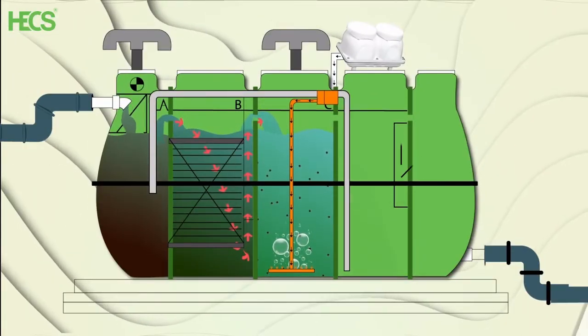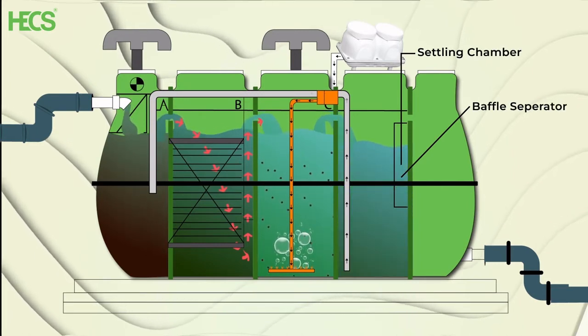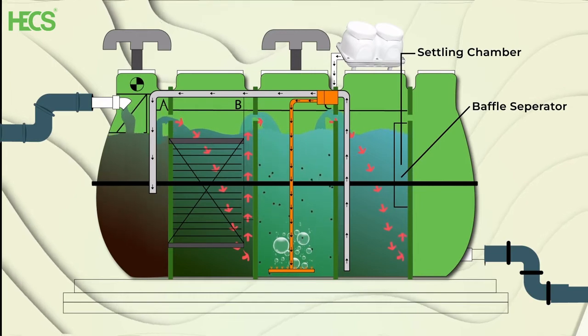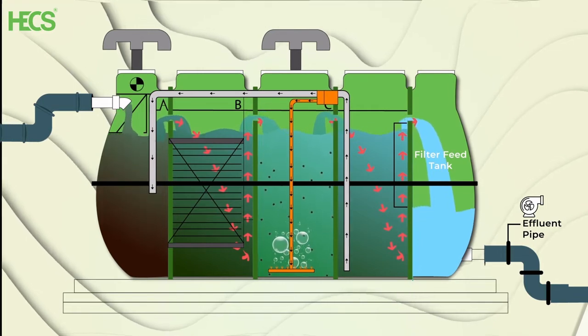The next chamber is a settling chamber. The activated sludge generated in the previous chamber settles down in this chamber and the same is recirculated into the first chamber through an internal recirculation line. The treated sewage then flows through a baffle separator into the filter feed tank, which is inbuilt in the STP system.